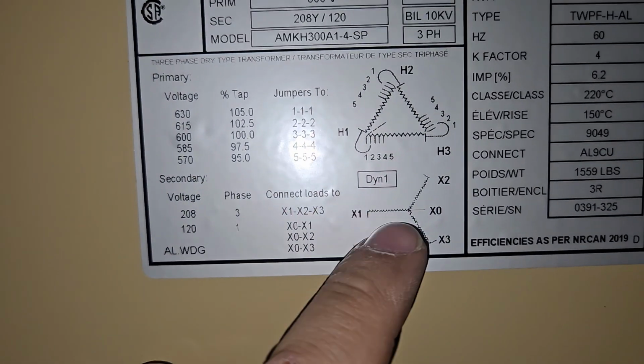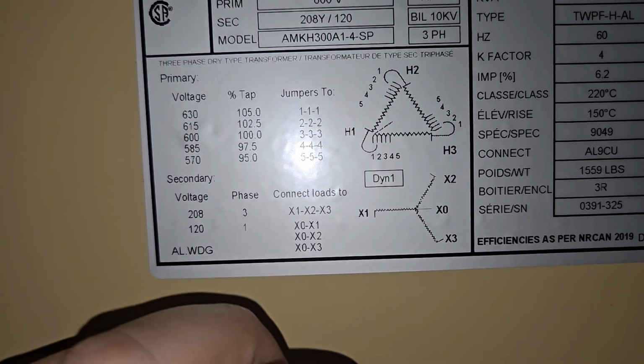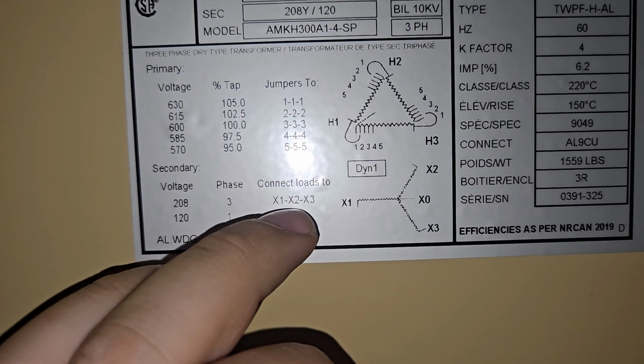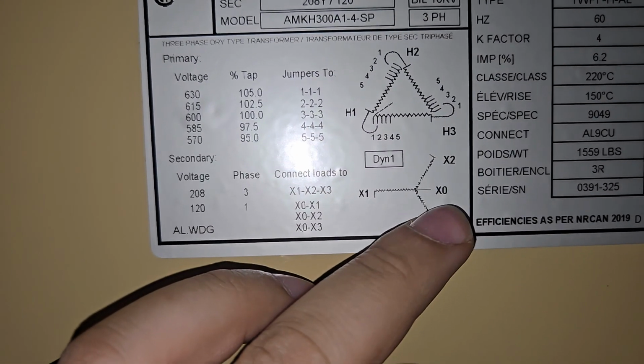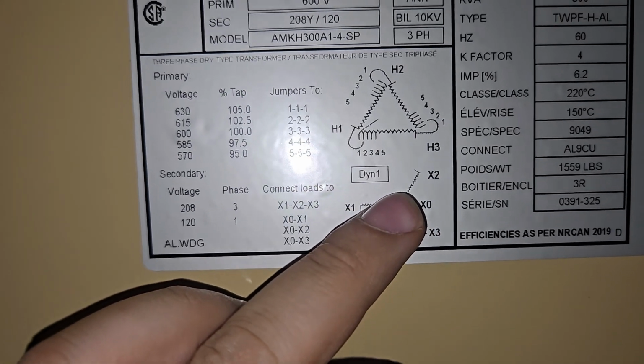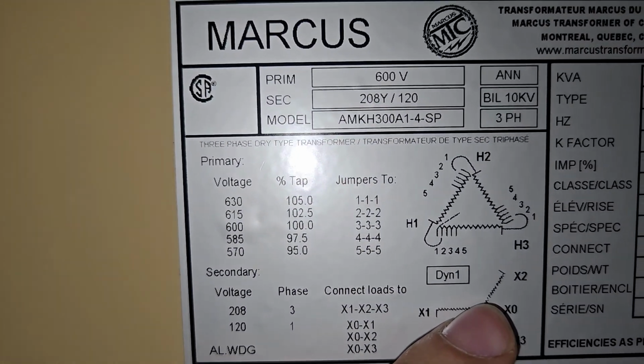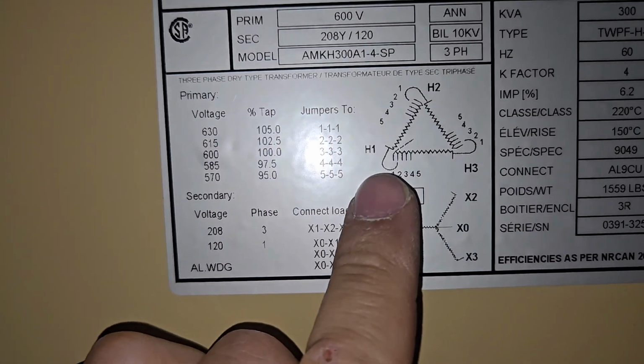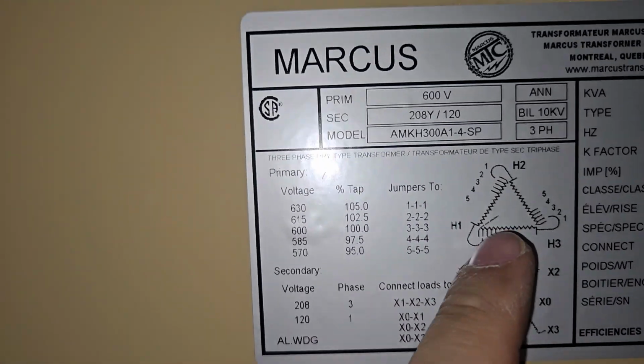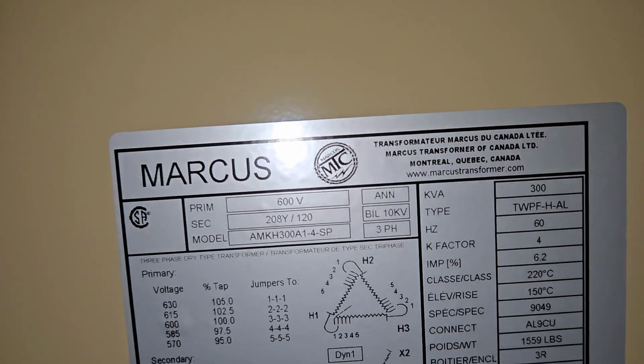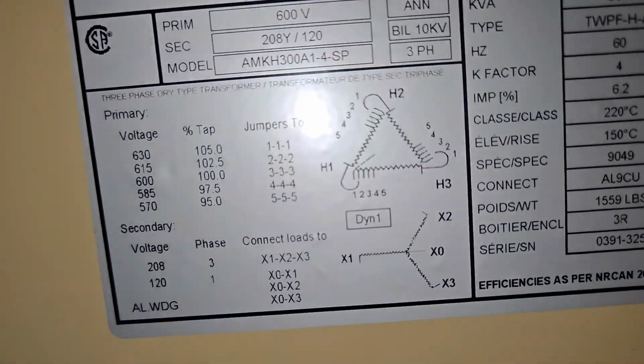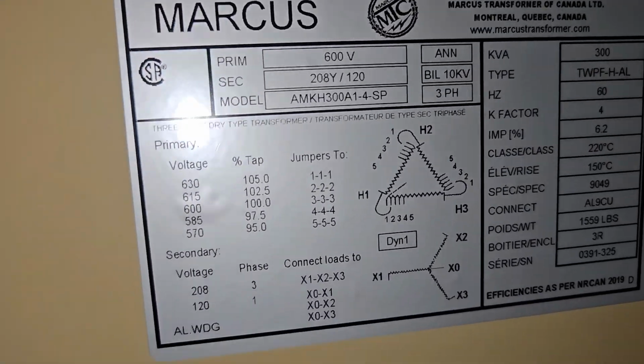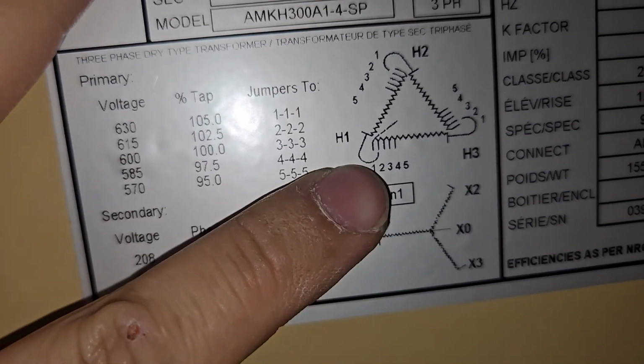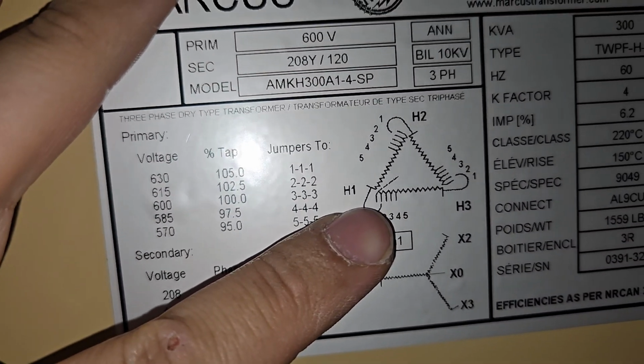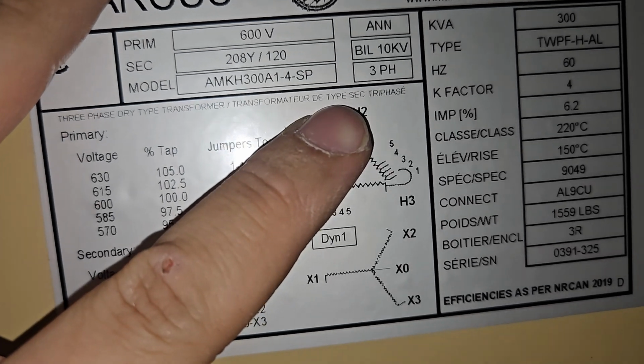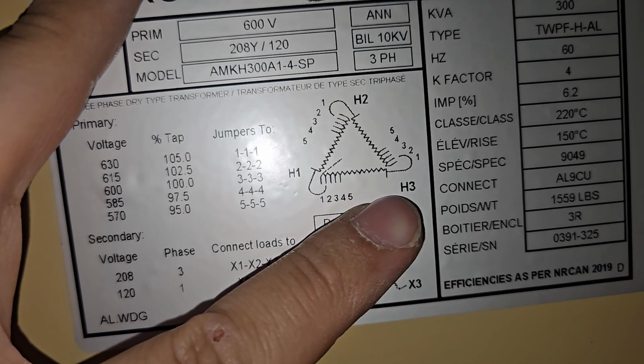But that can lead to trouble because your phases won't be balanced. Or you can connect a 3-phase panel to x1, 2, and 3, and you still have to use your x0 for your neutral to your panel. Now notice there's no neutral coming in. There's only a neutral going out. So the transformer is generating the neutral. Now, on the ends are H's. So there's H1, H2, and H3, which are the 3 phases coming in.